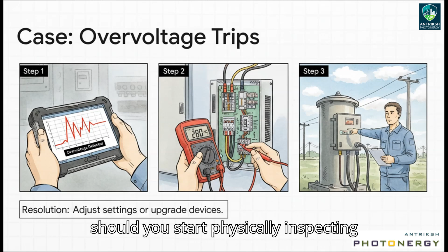You have to start with the data. Pull up the protection settings, look at the voltage logs from your SCADA system. Is the grid voltage actually high, or is something else going on? Only after you've looked at the data should you start physically inspecting things like wiring and connections. The relay itself is trying to tell you a story. It's packed with information. So learning how to read its event log or even just the front panel is a huge skill. This little table here is a great starting point.